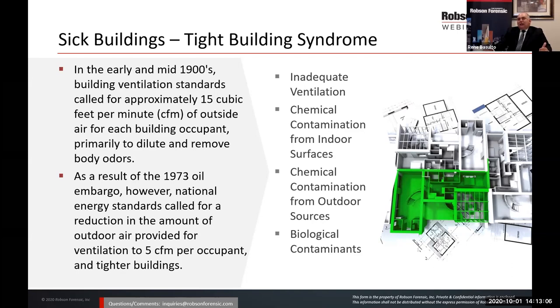As a result of the 1973 oil embargo, there were several issues that happened, and nationwide standards were established that called for, among other things, the reduction of outdoor air, providing only about 5 CFM per occupant. And that resulted in much tighter buildings, not only because they reduced the ventilation rate, but there were other factors involved in energy use reduction, whether it be insulation or tightening of windows. So what we ended up with is inadequately ventilated buildings, because we reduced the amount of air that we were introducing into the building. And that led to chemical contamination and buildup of chemicals inside the surfaces, because we didn't have enough air coming in to dilute it and ventilate the buildings.